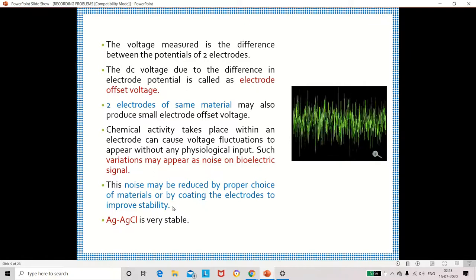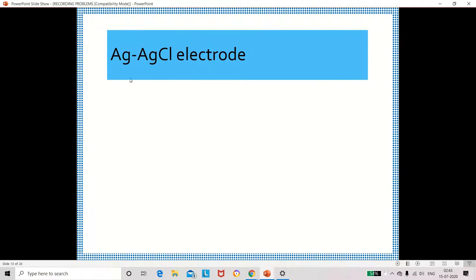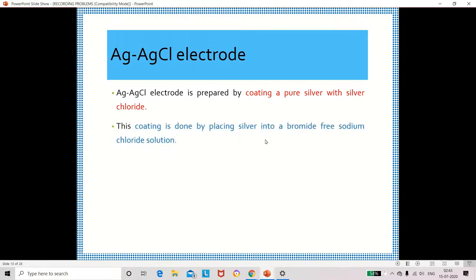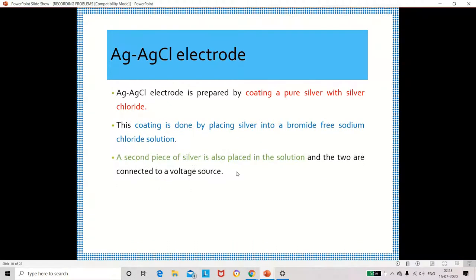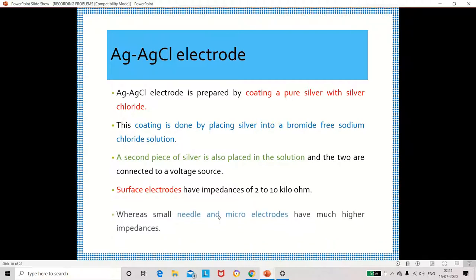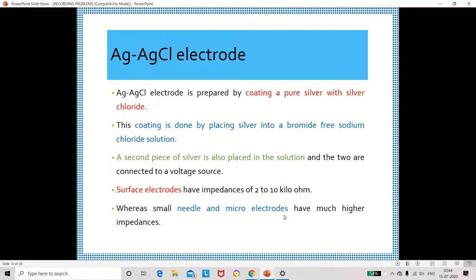We can reduce this noise by choosing proper material and coating the electrodes with proper material to improve stability. The best material for making the electrode is silver-silver chloride, which is very stable. To prepare a silver-silver chloride electrode, coat a pure silver with silver chloride and keep it in a bromide-free sodium chloride solution. For surface electrodes the impedance value will be 2 to 10 kilo ohms; needle or microelectrodes will have higher impedance.